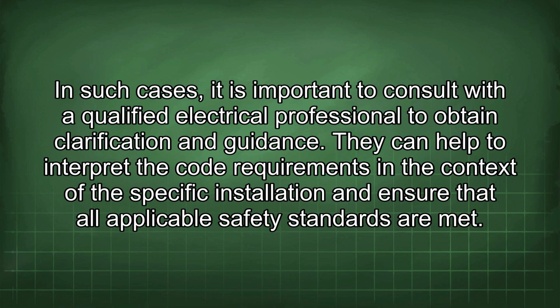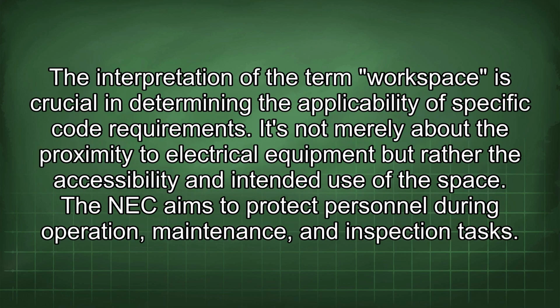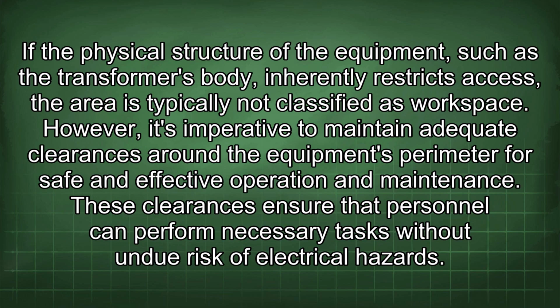They can help to interpret the code requirements in the context of the specific installation and ensure that all applicable safety standards are met. The interpretation of the term workspace is crucial in determining the applicability of specific code requirements. It's not merely about the proximity to electrical equipment, but rather the accessibility and intended use of the space. The NEC aims to protect personnel during operation, maintenance, and inspection tasks. If the physical structure of the equipment, such as the transformer's body, inherently restricts access, the area is typically not classified as workspace. However, it's imperative to maintain adequate clearances around the equipment's perimeter for safe and effective operation and maintenance. These clearances ensure that personnel can perform necessary tasks without undue risk of electrical hazards.